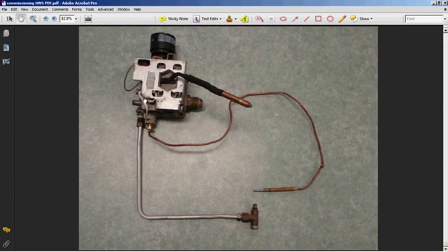This white wire here is a thermal fuse. On the end of that, there is a fuse that goes inside the hot water service alongside the bulb. So if for some reason the valve mucks up and the hot water service gets hotter and hotter and hotter, that fuse will actually melt, and all that is just running in circuit with the thermocouple.